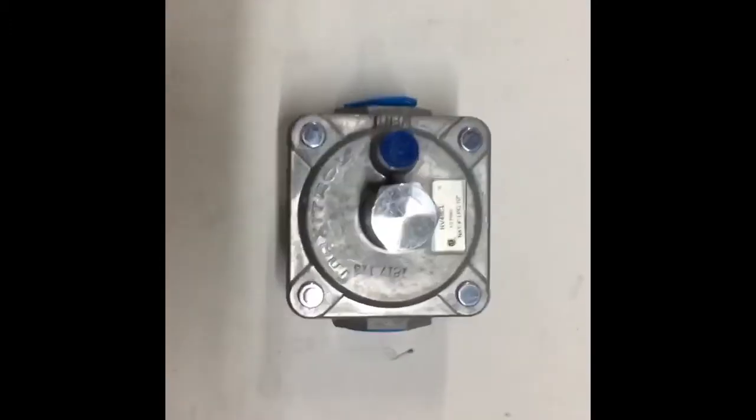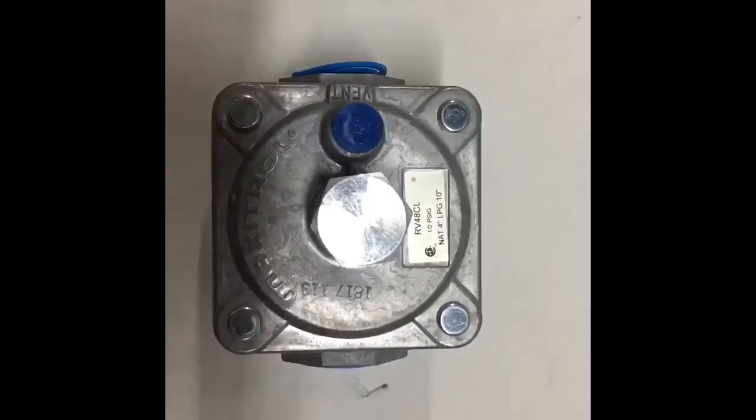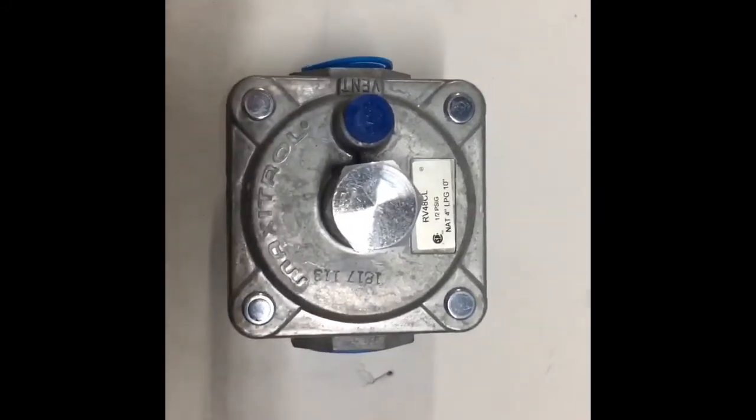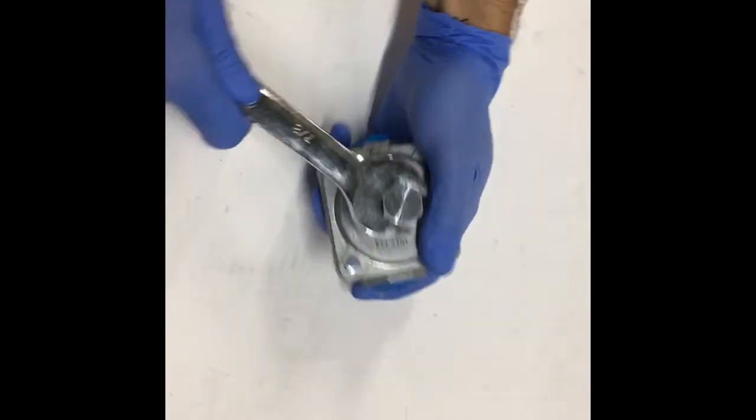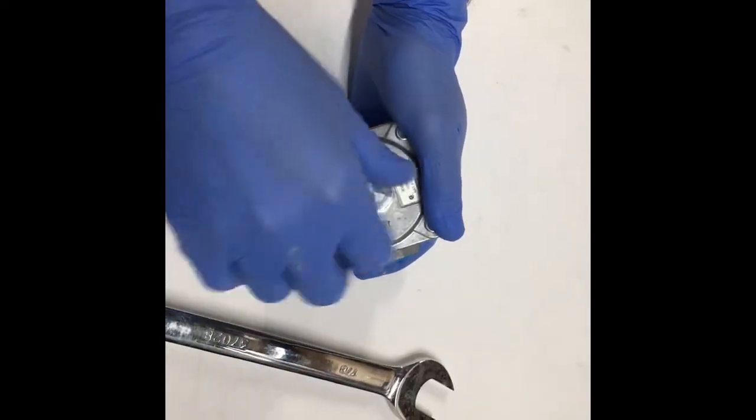Appliance regulators are only convertible when they have a hexagon shaped cap at the top of them. A circle cap will be preset for natural gas and cannot be converted.